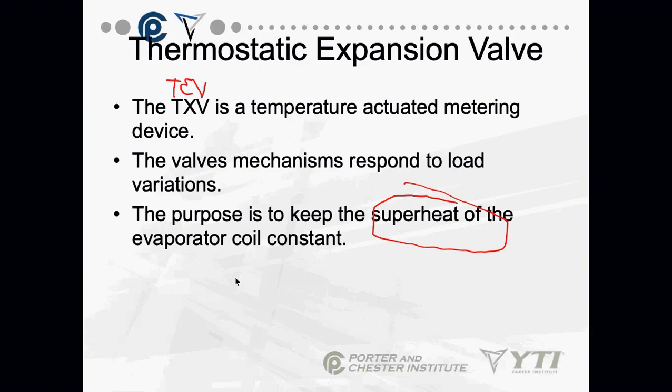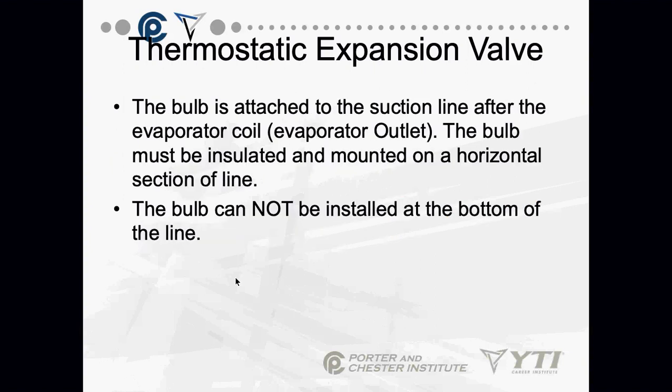As the load decreases, the refrigerant doesn't boil off as fast. The evaporator gets more full of liquid refrigerant. The superheat drops. The TXV starts to close because it maintains a superheat.